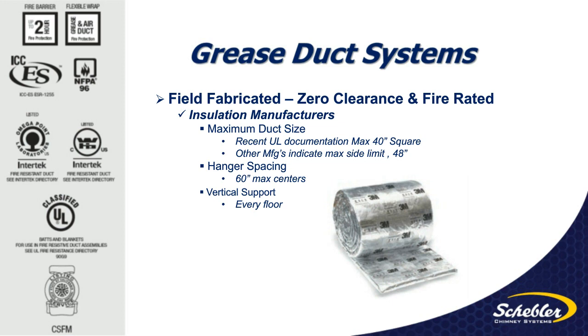Hangers and spacings, there's a reference to a spacing of possibly a maximum of 60 inches. And then an interesting note, I was able to find a note that vertical supports on ductwork that will be going up inside the building would need to be located on every single floor. I have yet to see that in construction, but it's pretty interesting to note that per the testing they've done, that was a requirement of them.